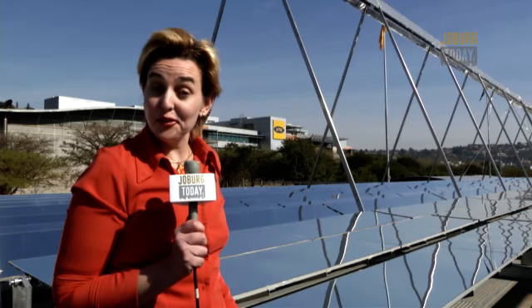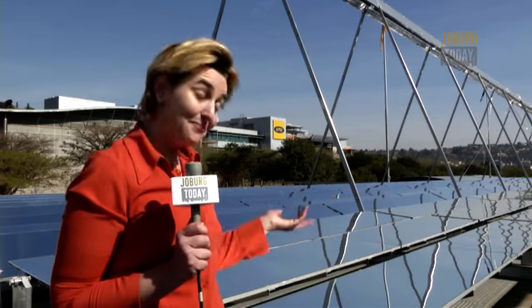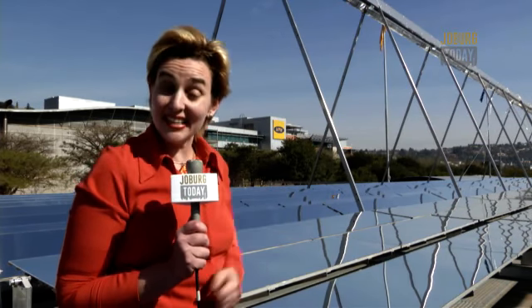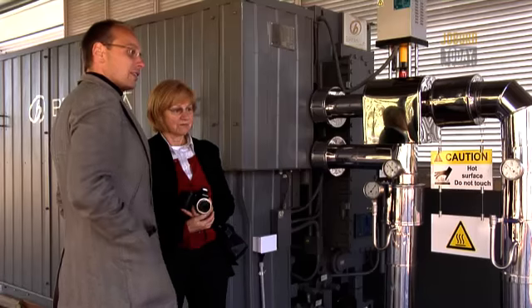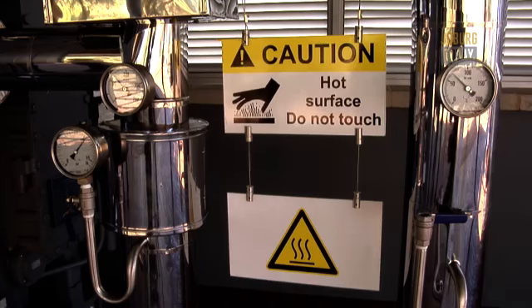One could be excused for being confused, as this plant uses the heat of the sun to, well, cool down the data center. A concentrating solar cooling system allows us to produce higher temperature heat, in this case 180 degrees, and with that power a double effect absorption chiller, which is a higher efficiency absorption chiller, producing more cooling from the same amount of heat than would be possible with other solar technologies.